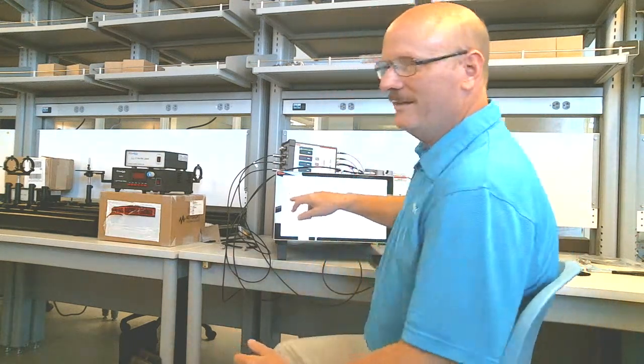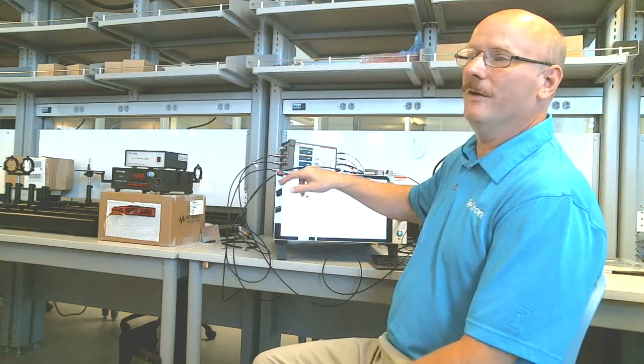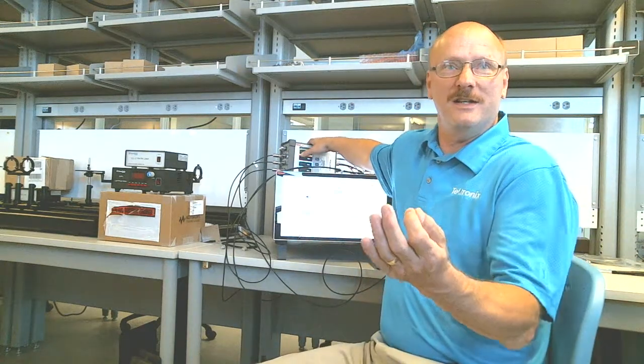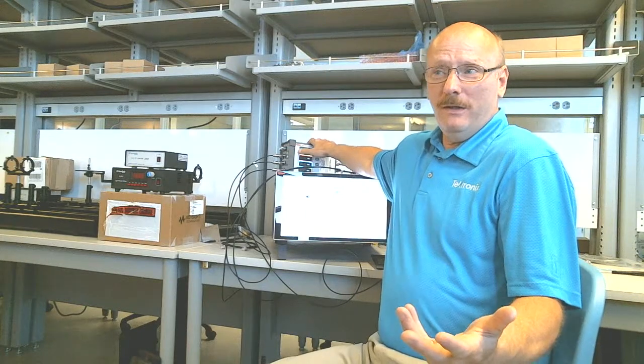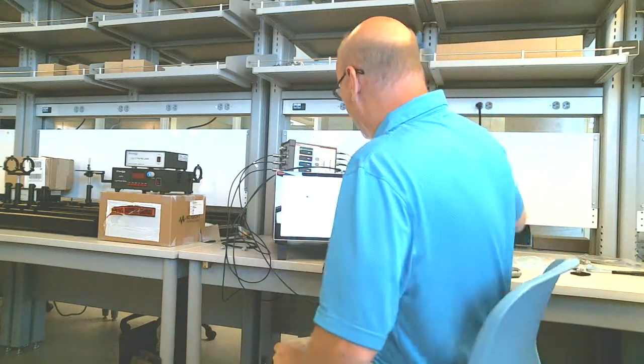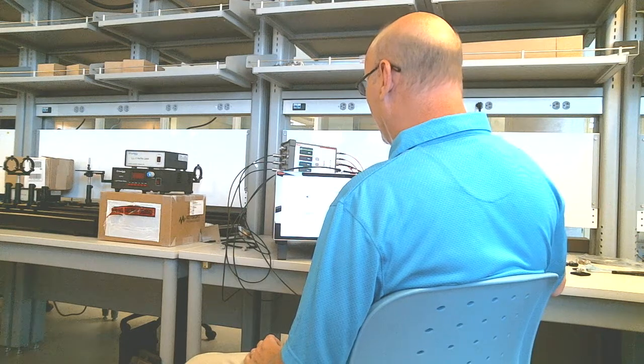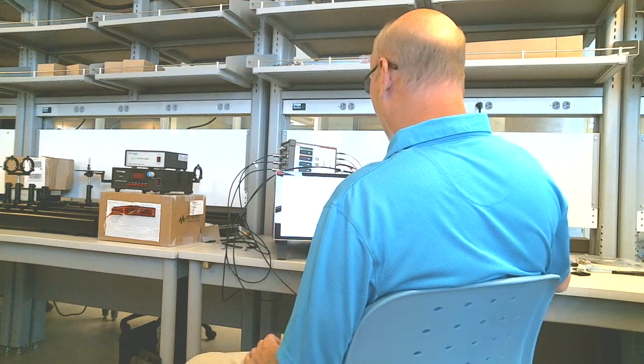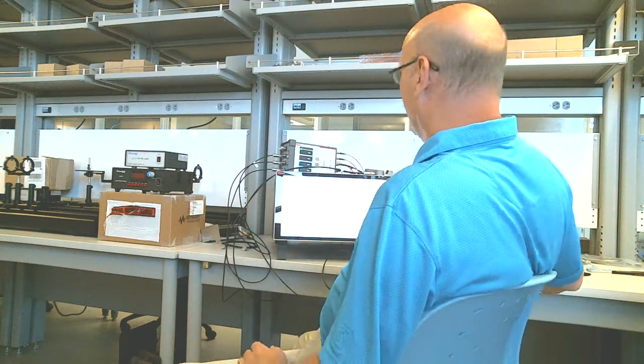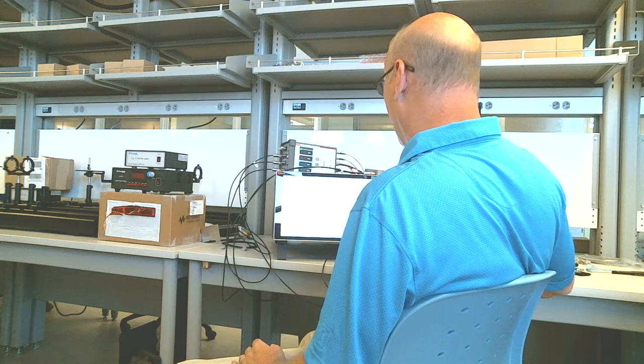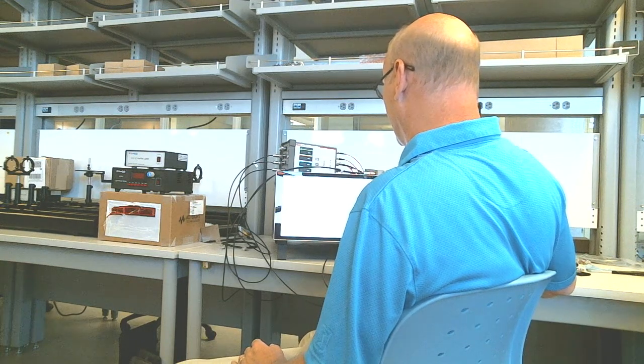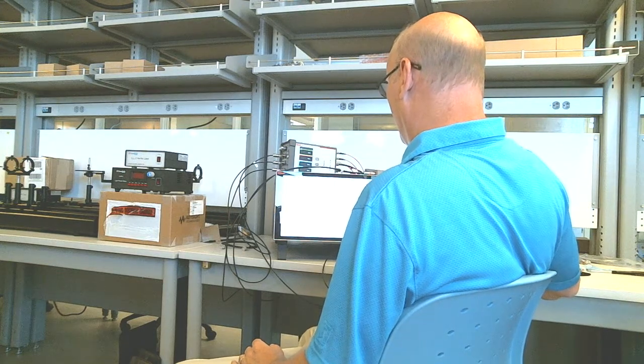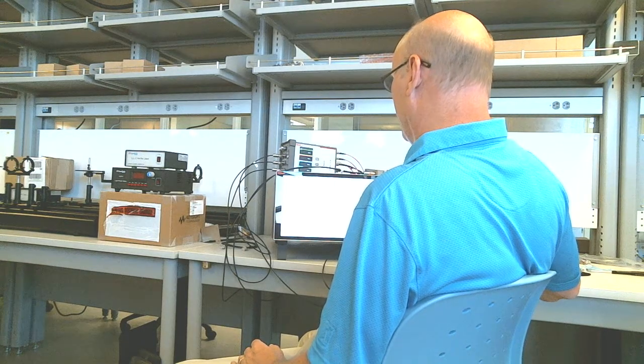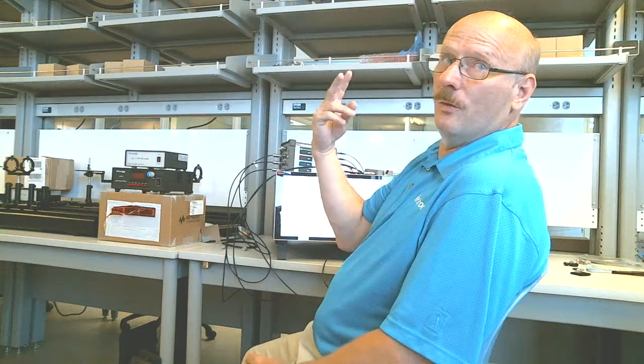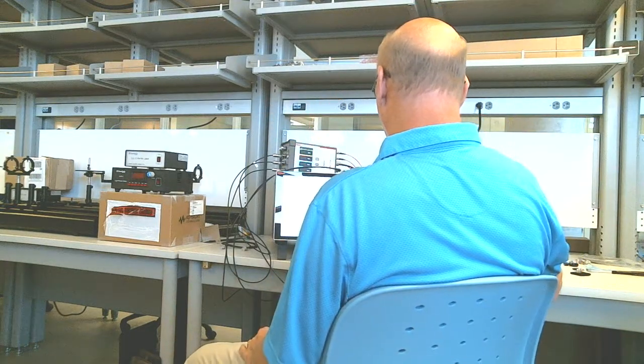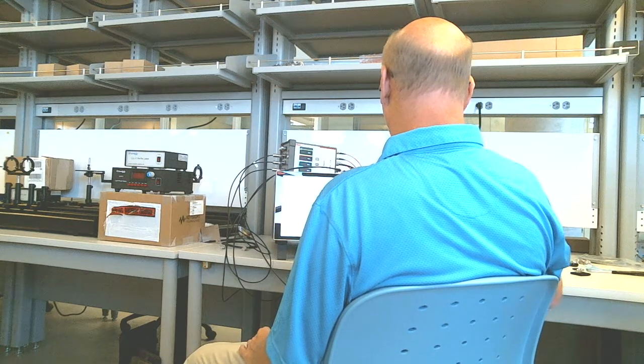Before I can do any DC tests, I need to configure the CV-IV box for DC. My options are open, DC, or CV. So now I go to this test, go to configure, and tell it what I want on each channel. Channel 4 we don't have, because we're missing that pass-through, so I'll set it to open. I'm going to do a 2-wire setup, here's where I select 2-wire or 4-wire. I'm only using one cable, so it's 2-wire. And then I can put the names of the pins over here if I want to.